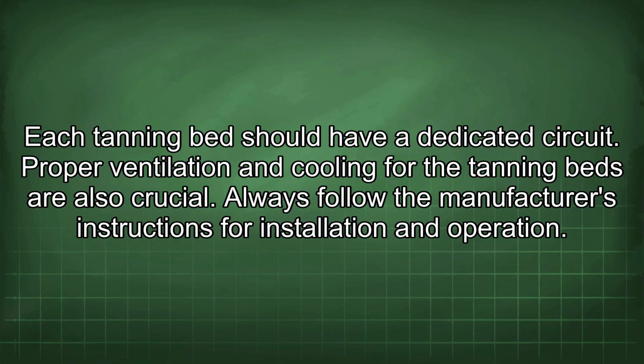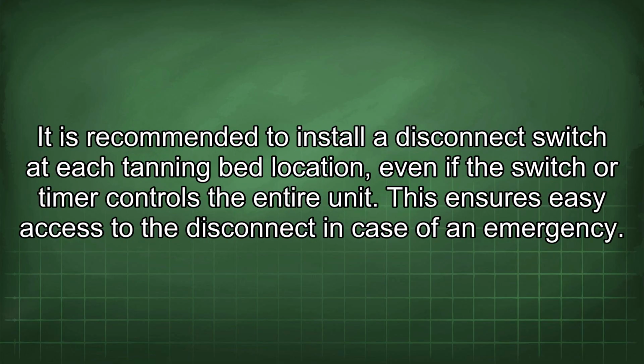Proper ventilation and cooling for the tanning beds are also crucial. Always follow the manufacturer's instructions for installation and operation. It is recommended to install a disconnect switch at each tanning bed location, even if the switch or timer controls the entire unit. This ensures easy access to the disconnect in case of an emergency.